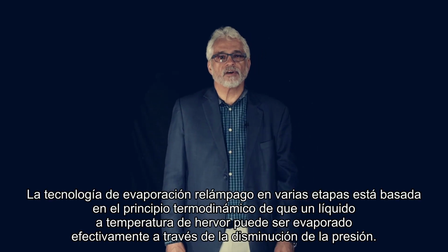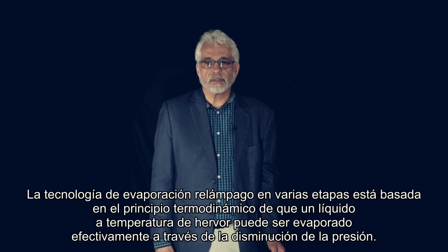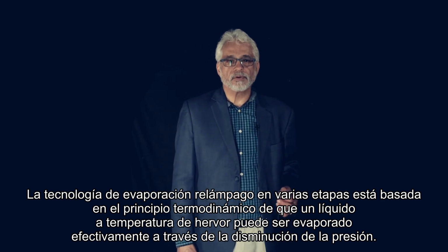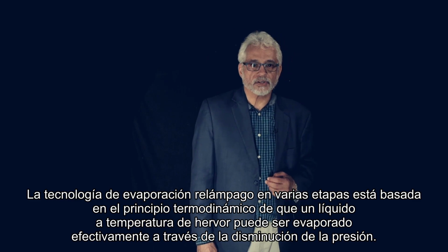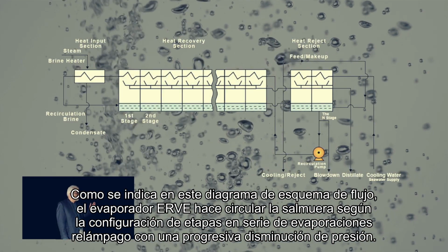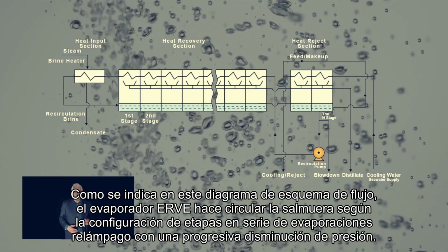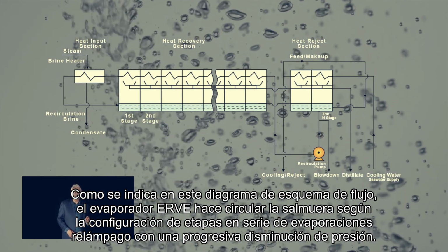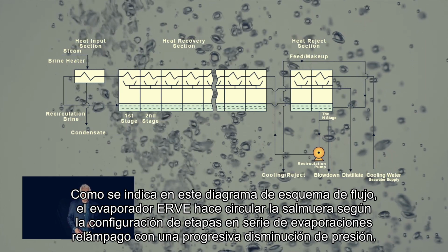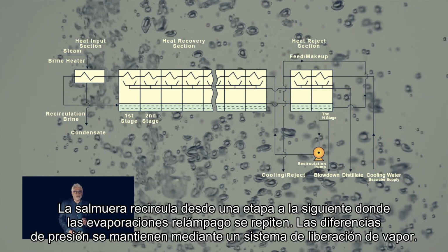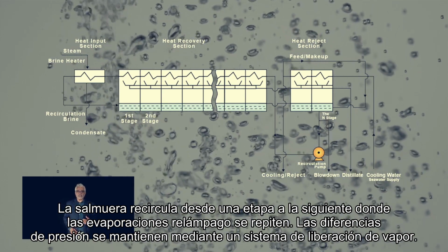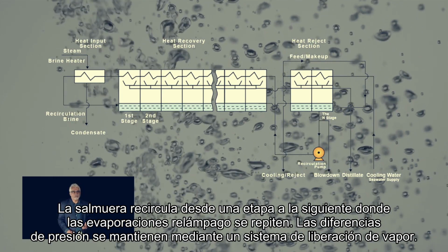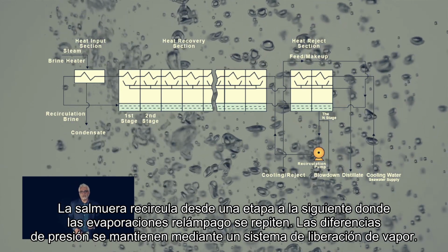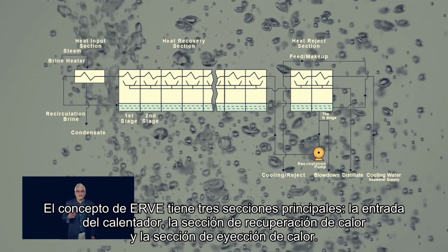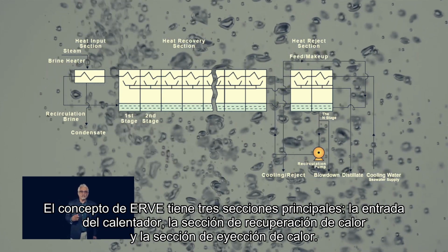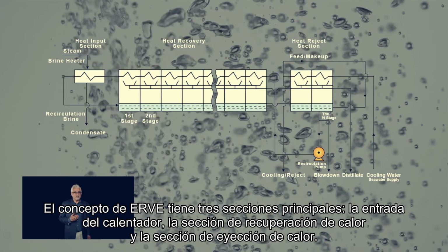The multi-stage flashing technology is based on the thermodynamic principle that a liquid at boiling temperature can be evaporated effectively through pressure reduction. As indicated in this schematic flow diagram, the MSF evaporator with brine recirculation is a configuration of flashing stages in series at succeeding lower pressure, and the recirculation brine from one stage flows to the next stage where the flashing process is repeated. Pressure difference in the stages is maintained by a steam ejector system. This MSF concept has three main sections: the heat input, the heat recovery, and the heat rejection section.